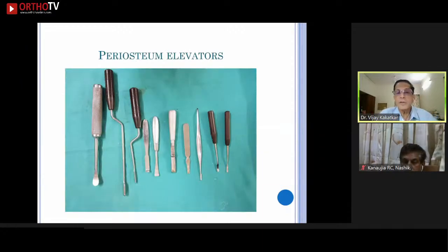Then these are different types of periosteum elevators. This particular design is called a Cobb's periosteum elevator. You can get it in various sizes. These are the two periosteum elevators which are used for minimally invasive surgery, and they have a hole at the tip.